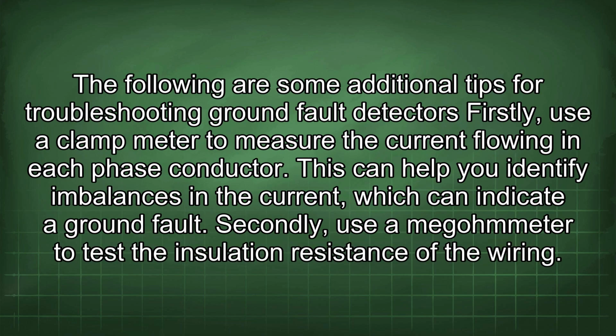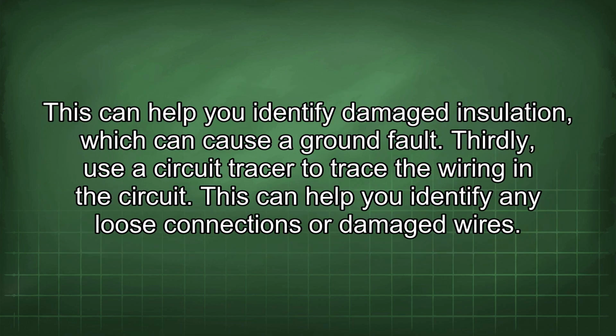The following are some additional tips for troubleshooting ground fault detectors. Firstly, use a clamp meter to measure the current flowing in each phase conductor. This can help you identify imbalances in the current, which can indicate a ground fault. Secondly, use a megohmmeter to test the insulation resistance of the wiring. This can help you identify damaged insulation, which can cause a ground fault. Thirdly, use a circuit tracer to trace the wiring in the circuit. This can help you identify any loose connections or damaged wires.